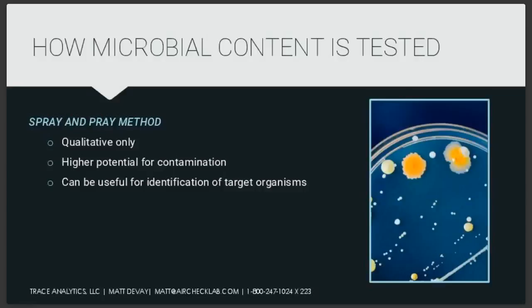The sampling is typically a little bit cheaper. The device that you're using is a lot less expensive. But you have to keep in mind the only information that you can get out of this that's particularly useful is what you have. So if your specifications require you to know how many microbes or how many viable particles you have in your gas, this is not going to be suitable for that. The other thing is this has a fairly high potential for contamination, but it is really useful if you need to know whether or not you've got Salmonella or Listeria in your lines.